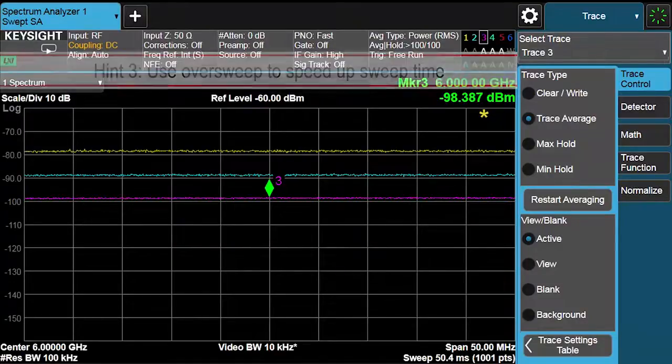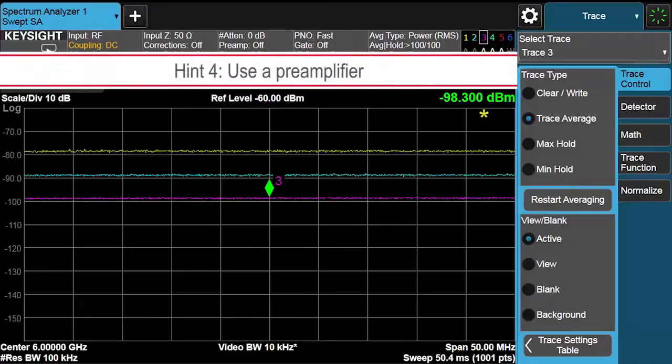Another technique to improve sensitivity is to use the analyzer's internal pre-amplifier. The internal pre-amplifier can greatly improve analyzer sensitivity, and one might ask the question, why not use the internal pre-amplifier all of the time? The answer is that if you're measuring high-powered signals in the presence of low-powered signals, and the pre-amplifier is turned on, then you can compress or overload the analyzer's mixer, resulting in distortion of your measurement.